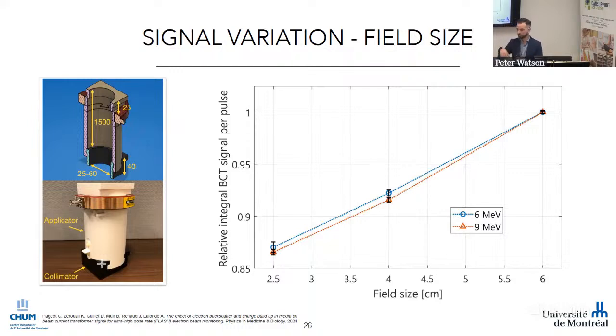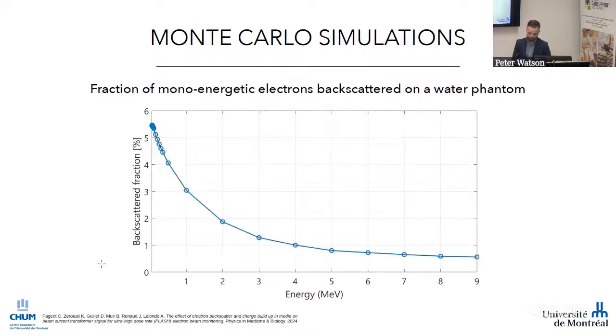You have a larger area of the collimator exposed to the beam, so potentially more backscatter. So here again, about 15% signal difference for a smaller versus larger field size. That is what we observed, and it is in line with what was in the literature. So we wanted to understand what was happening with all this backscatter.